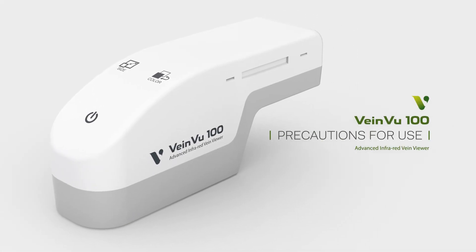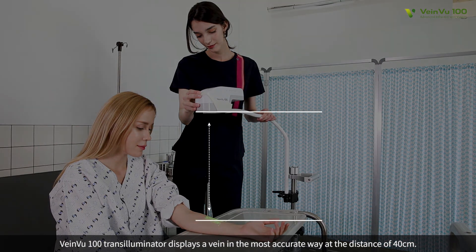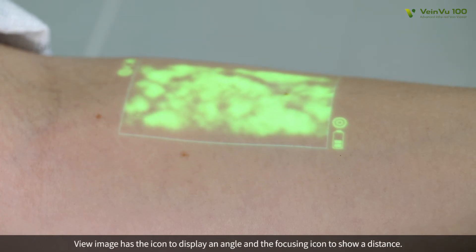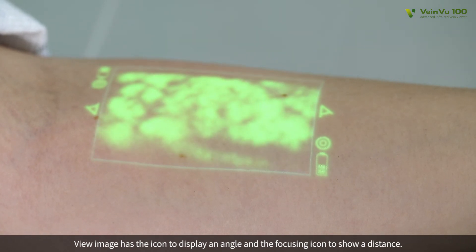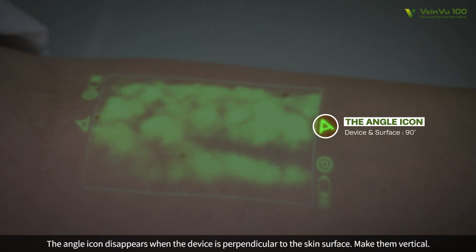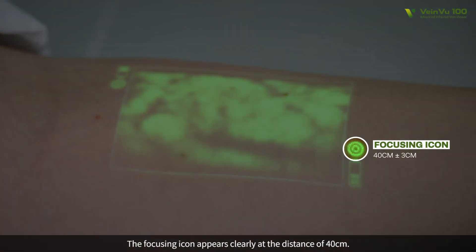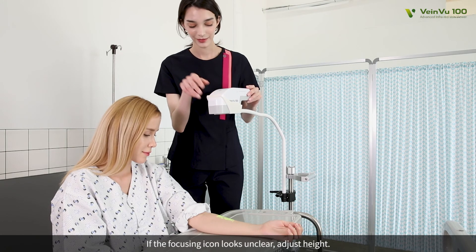Precautions for Use. VeinVu 100 Transilluminator displays a vein in the most accurate way at a distance of 40 centimeters. The view image has an icon to display an angle and a focusing icon to show distance. The angle icon disappears when the device is perpendicular to the skin's surface — make them vertical. The focusing icon appears clearly at 40 centimeters. If the focusing icon looks unclear, adjust the height.